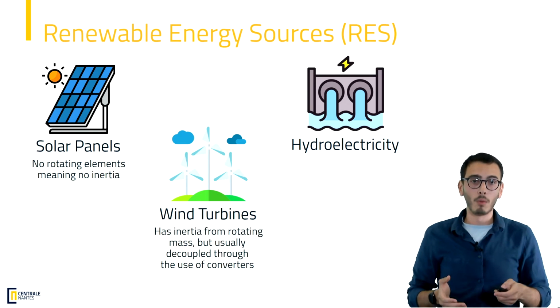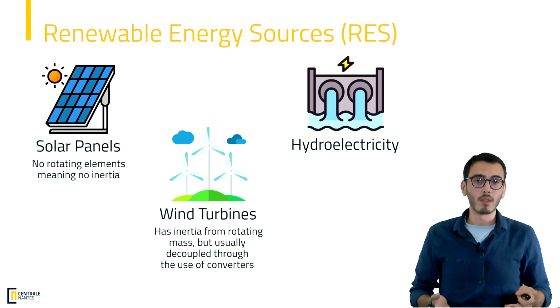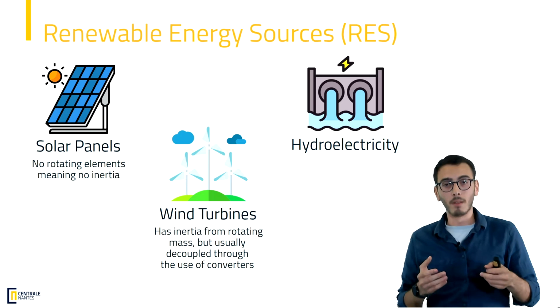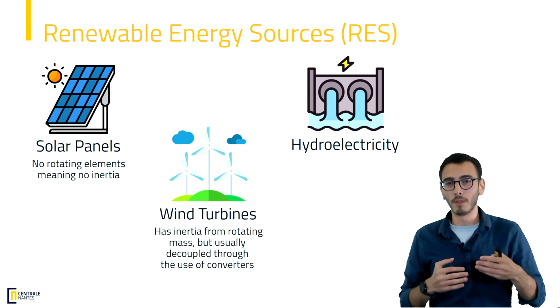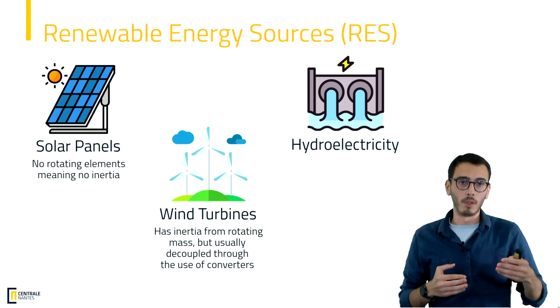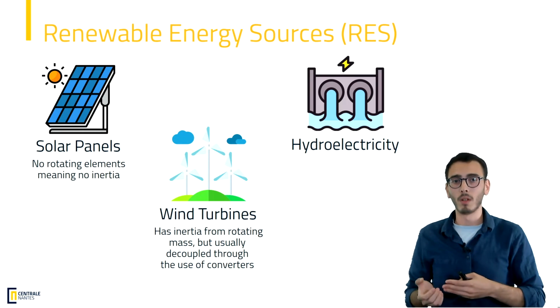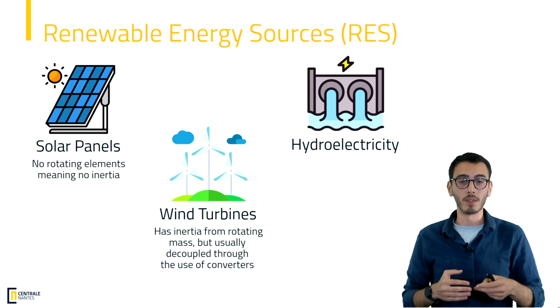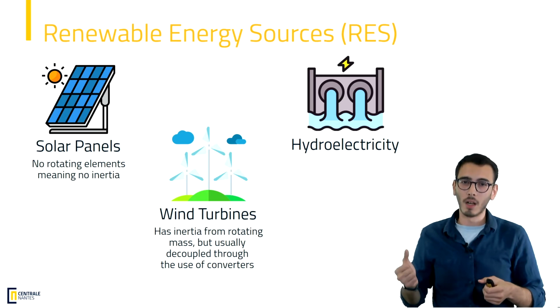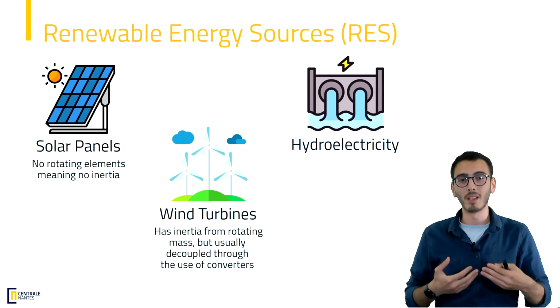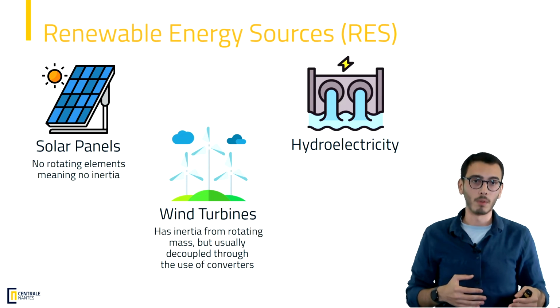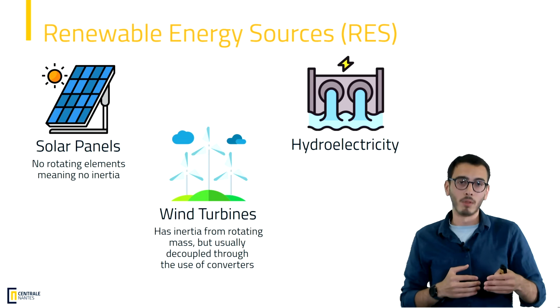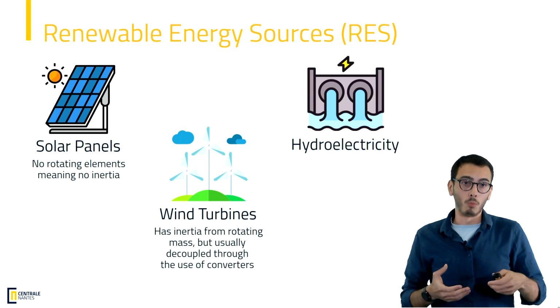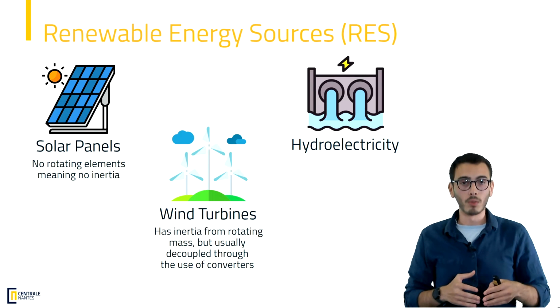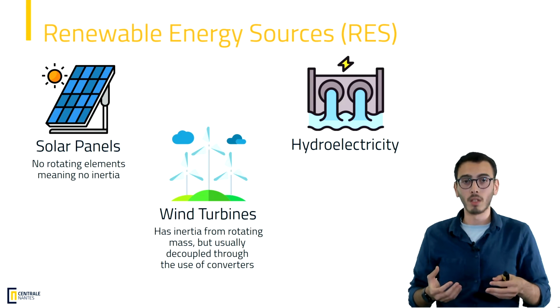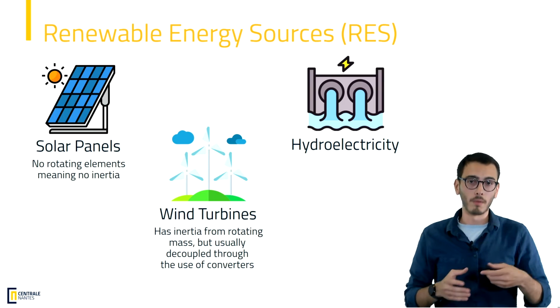In terms of wind turbines, well, basically there are rotating elements. It's based on a rotating element. But the problem is that the wind turbine is running at a different speed or a different frequency from the grid. As you remember, in France the grid frequency is 50 hertz, while the wind turbine runs at varying frequencies. That means we cannot supply this electricity directly from the wind turbine to the grid, because it will create a lot of disturbances because of this varying frequency. So we have to decouple the energy created from the grid. Usually it's decoupled through a converter, which I'm not going to go into, but it just means that the inertia is actually not being used in the grid because of this decoupling.